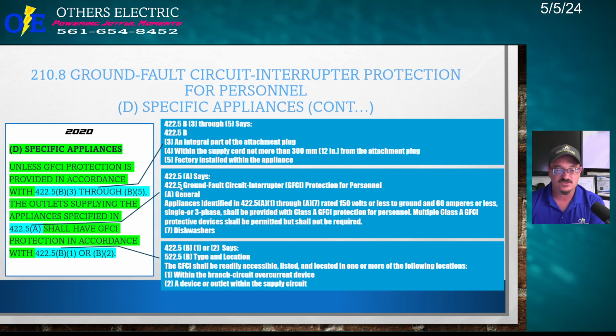So what is in 422.5A? Well, let me tell you. 422.5A says, ground fault circuit interrupter, protection for personnel, general. So confusing. Okay. Appliances identified in 422.5A1 through A7 rated 150 volts or less to ground and 60 amperes or less, single or three-phase, shall be provided with Class A GFCI protection for personnel. Multiple Class A GFCI protected devices shall be permitted but shall not be required. So what I'm going to do is go through that. It gets a little hairy around there.